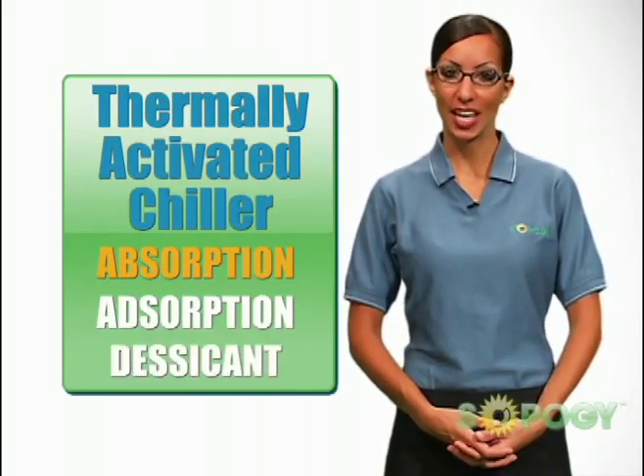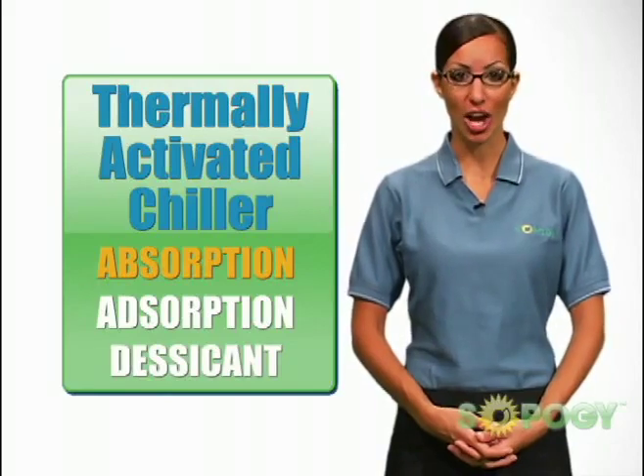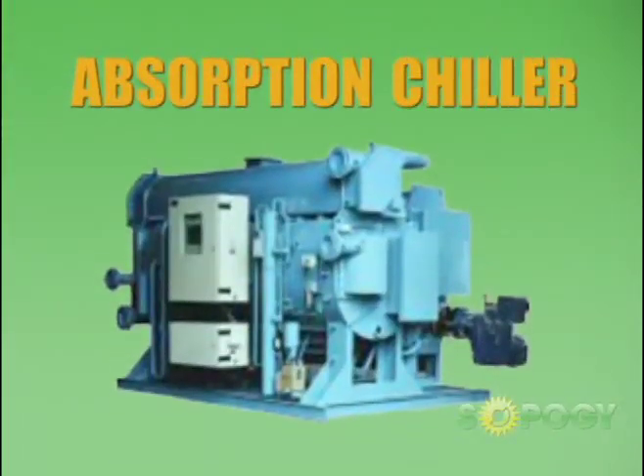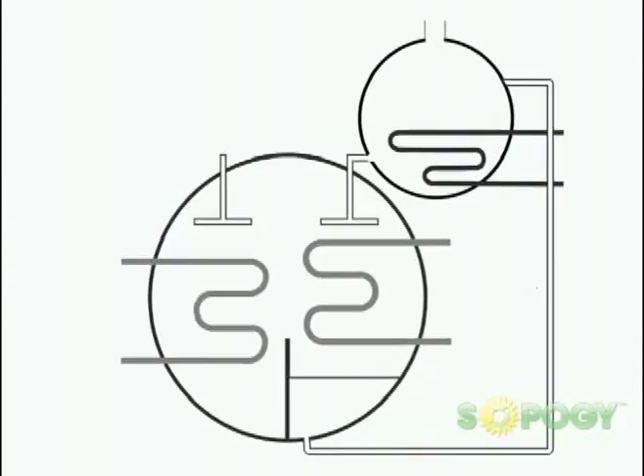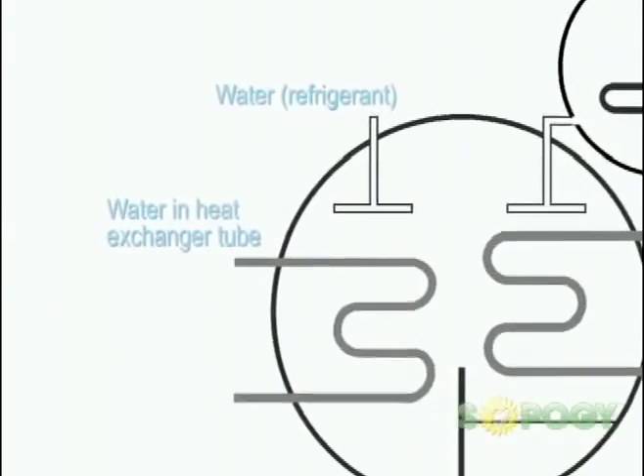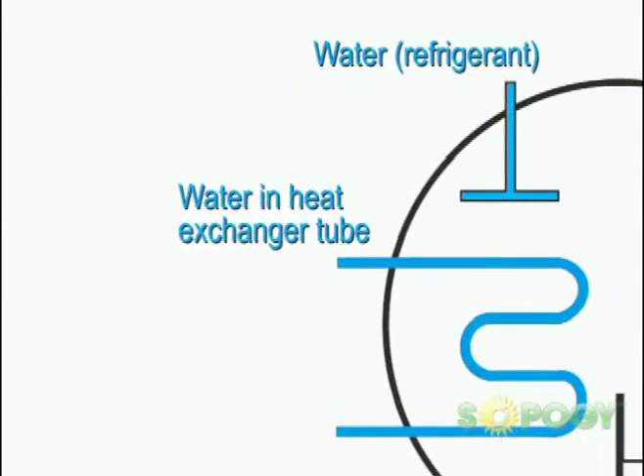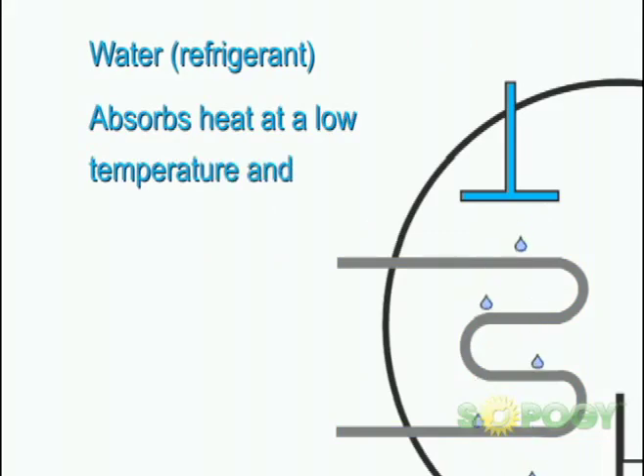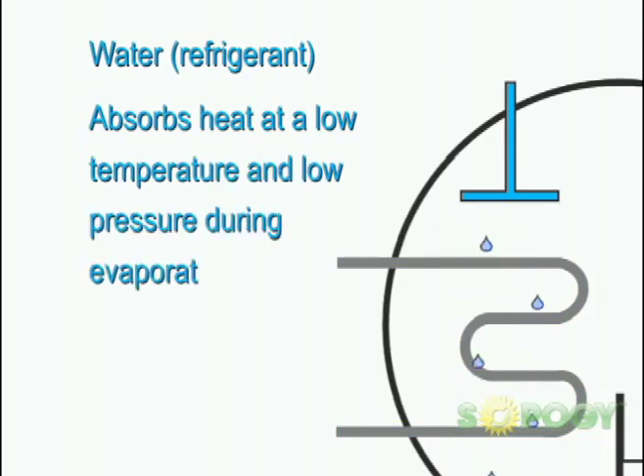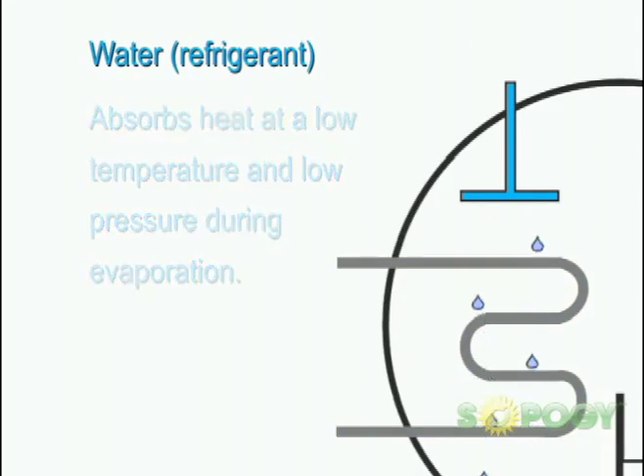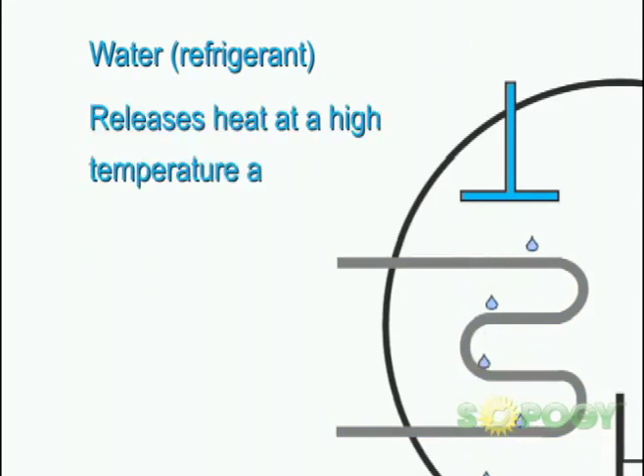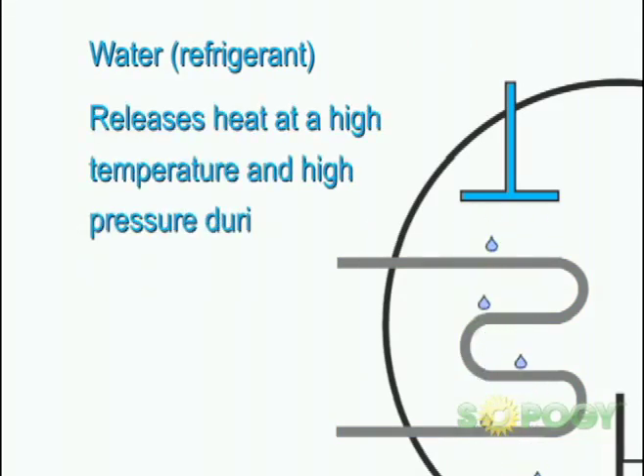Adsorption and desiccant chillers are less common, so we'll focus on the absorption chiller principle. In these systems, water — the refrigerant — absorbs heat at a low temperature and low pressure during evaporation, and releases heat at a high temperature and high pressure during condensation.